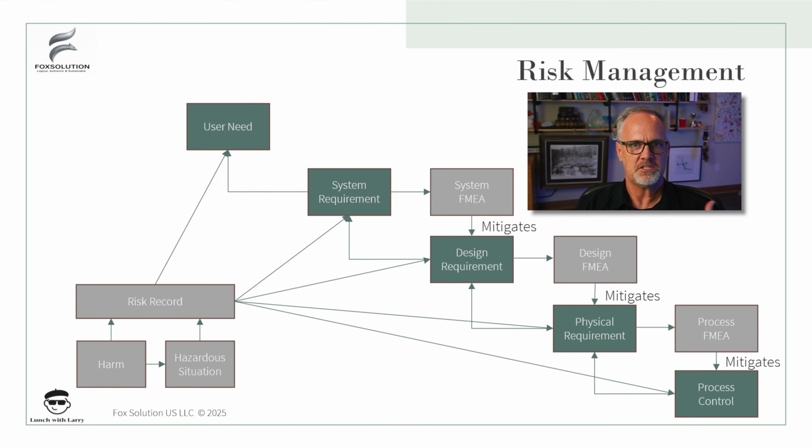And then this sterilization question I had, how often the harm is exposure of the user to a non-sterile device. There's all kinds of things that need to happen to assure that that hazardous situation where that exposure happens doesn't occur. So things from aseptic transfer techniques, storage, the sterilization process itself, all the design requirements around the design of the sterile barrier bag, for example. So all kinds of things that we need to take into account when we say that we've controlled that hazardous situation. Really needs to be a systems level view.